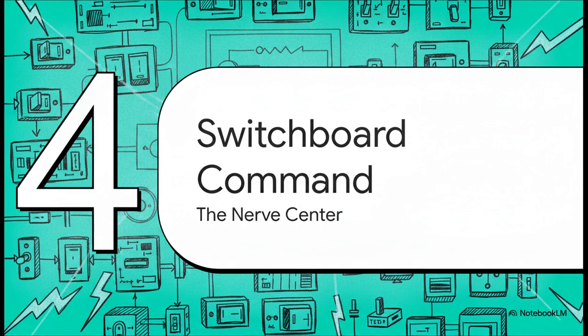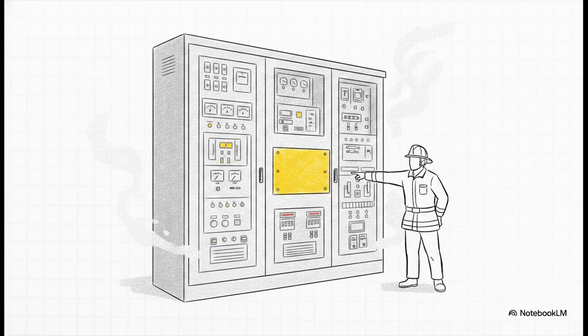Finally, part 4, the switchboard command center. Because this is the command center, there can be absolutely zero ambiguity about what it is. The rules are crystal clear. It shall be legibly and permanently marked main switchboard. If smoke is pouring into a building or a technician needs to kill the power right this second, there's just no time for guessing. The command center has to be immediately identifiable to anyone, especially emergency responders.